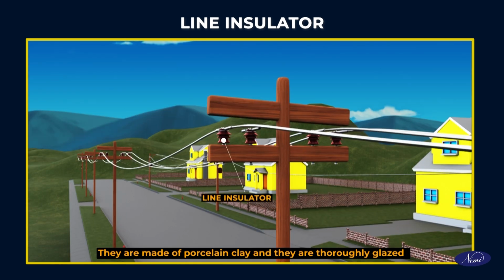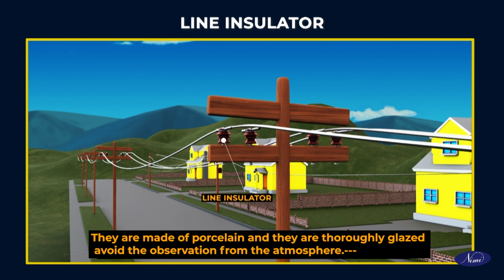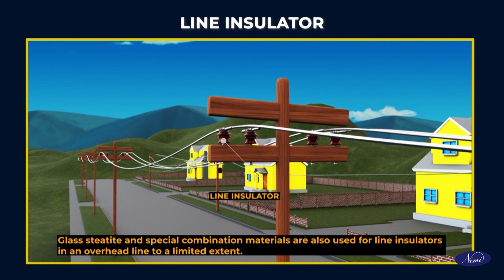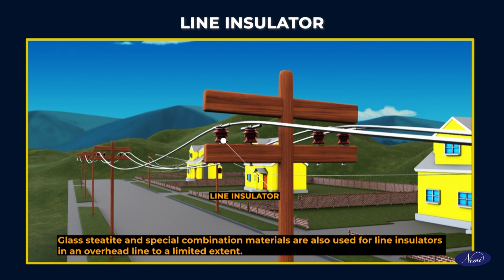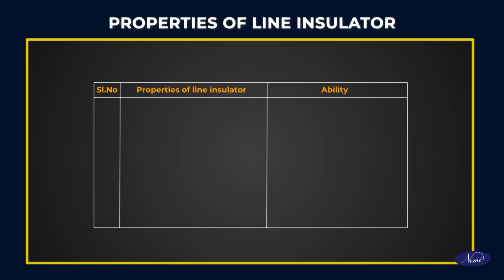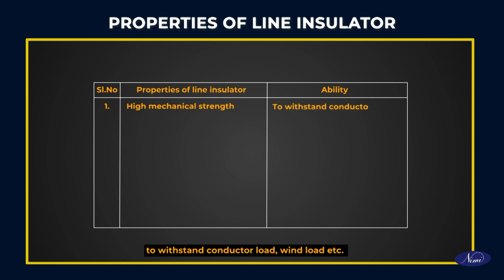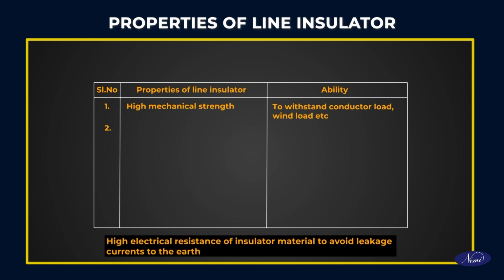They are made of porcelain clay and they are thoroughly glazed to avoid the absorption of moisture from the atmosphere. Glass, steatite and special combination materials are also used for line insulators in an overhead line to a limited extent. Properties of line insulator: high mechanical strength to withstand conductor load, wind load, etc. High electrical resistance of insulator material to avoid leakage currents to the earth.